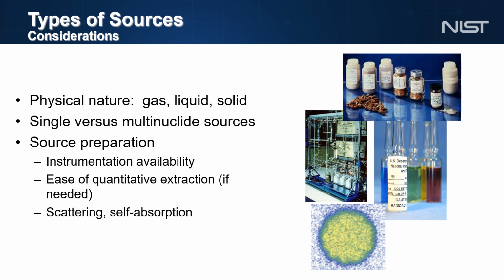The radionuclide metrologist encounters many types of sources: gas, liquid, and solid. Matrices such as soils, building materials, and biologically derived samples can further complicate measurement and generally add to self-absorption issues. In addition, sources may contain multiple radionuclides, including potential impurities. Whether measurements are more appropriate on an intact sample, or if radionuclides of interest need to be extracted, are also considered in choosing a measurement method.